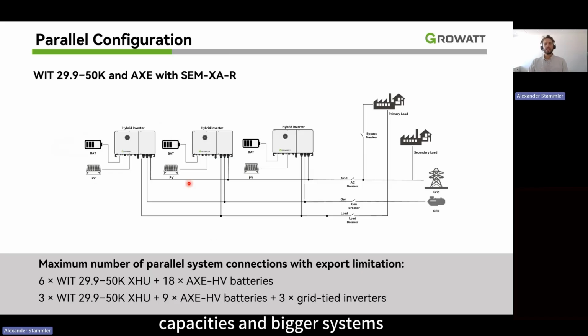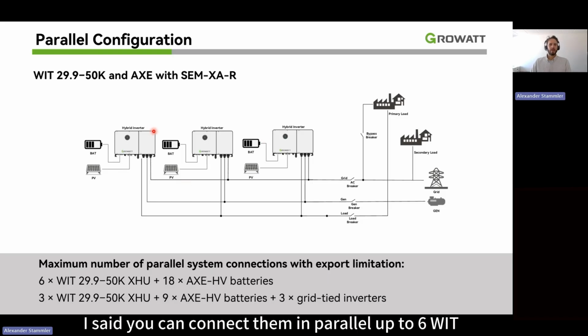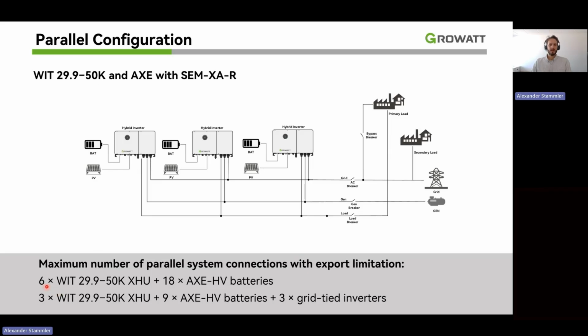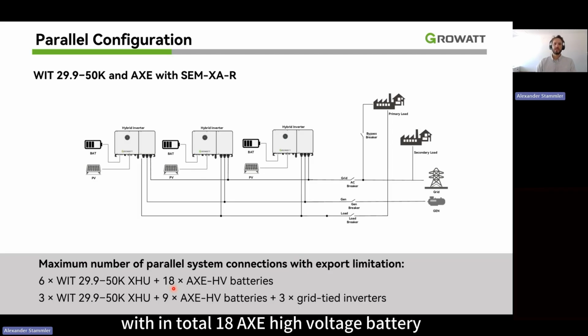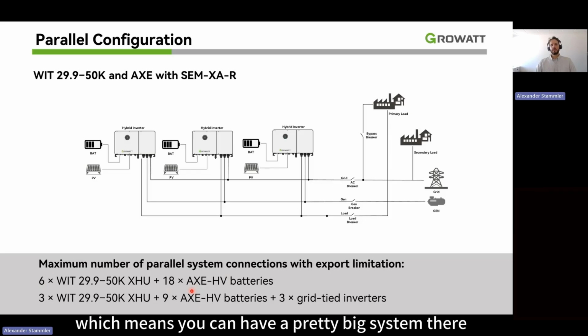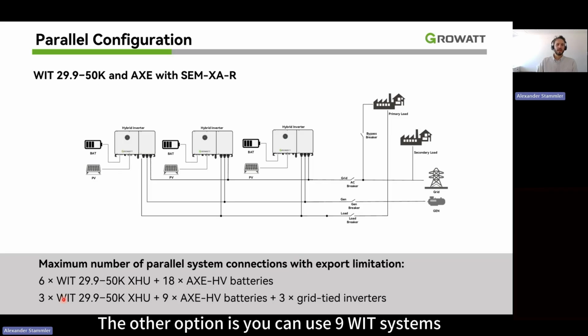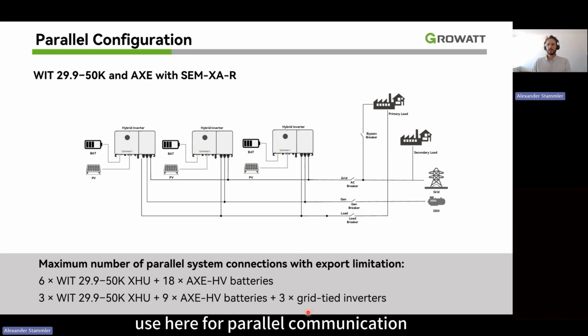If you want to create bigger capacities and bigger systems, I said you can connect them in parallel up to 6 WIT with in total 18 AXE high voltage batteries. So each of the WIT with 3 batteries, 3 times 6 is 18 batteries, which means you can have a pretty big system there. The other option is you can use 3 WIT systems plus 9 AXE high voltage batteries plus 3 grid-tied inverters. So there are some options you can use here for parallel communication. Also, the generator can be connected to each of the generator ports in total, and you can connect the backup connectors of the inverters in parallel to the primary load, so that the primary load is fed by the 3 different inverters.